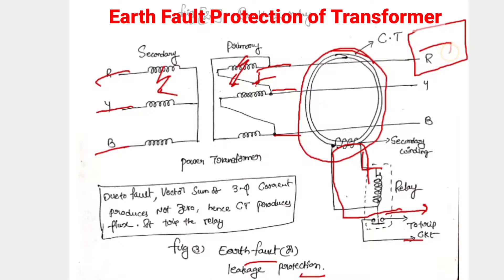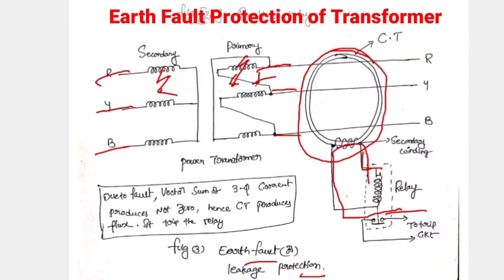If any fault occurs, due to the vector sum of three-phase currents being non-zero, the CT produces a flux. The CT secondary having this flux will cause a current to flow through the relay coil. Due to flux in the CT, a voltage or current is produced in the secondary winding, which flows through the relay coil. The CT detects the earth fault or winding fault before it becomes dangerous and operates the relay coil.